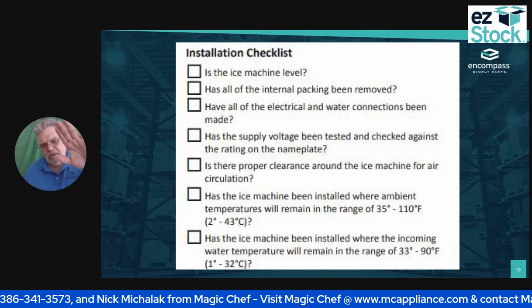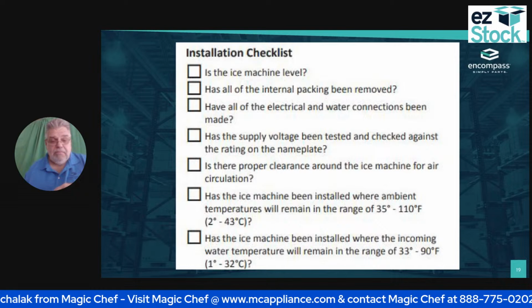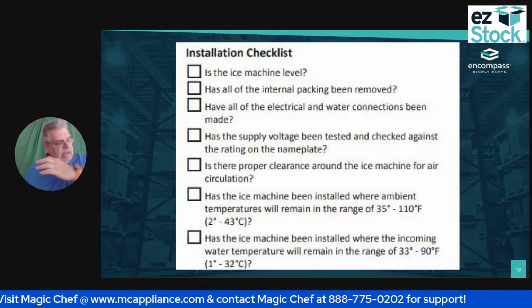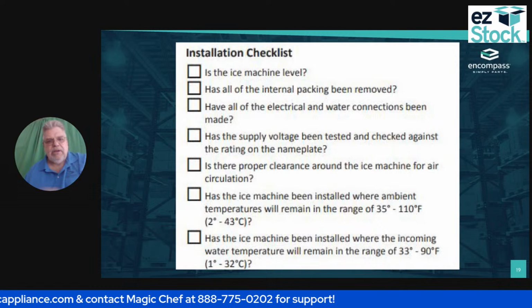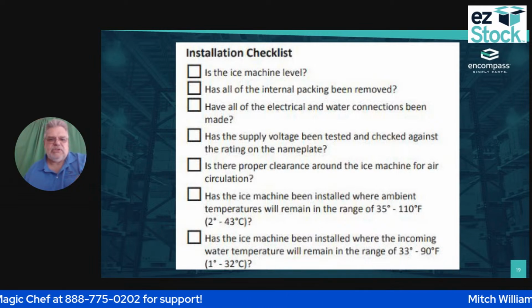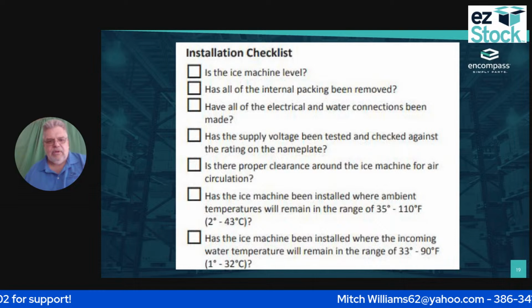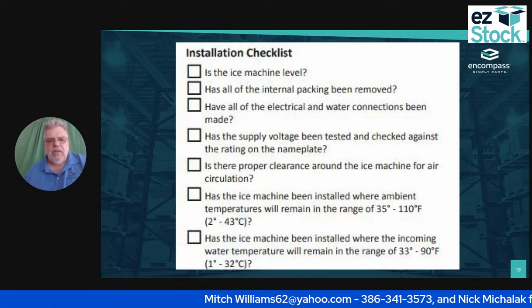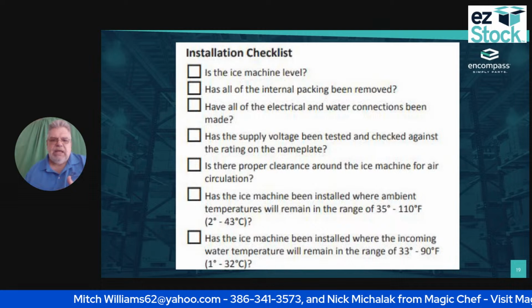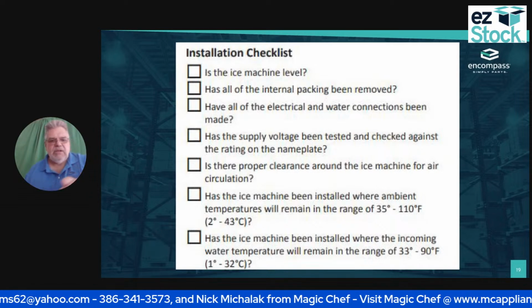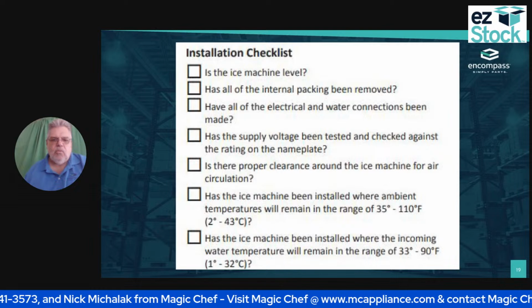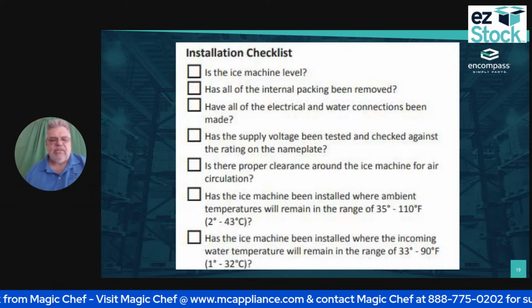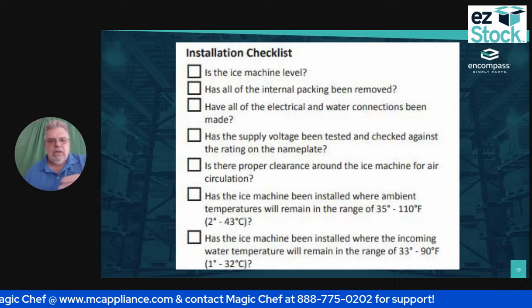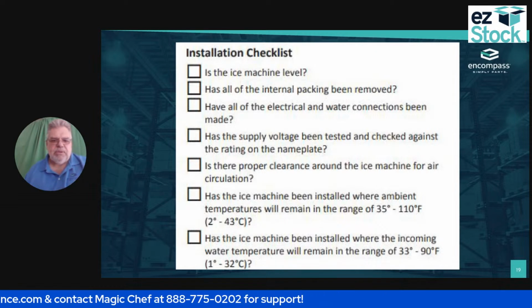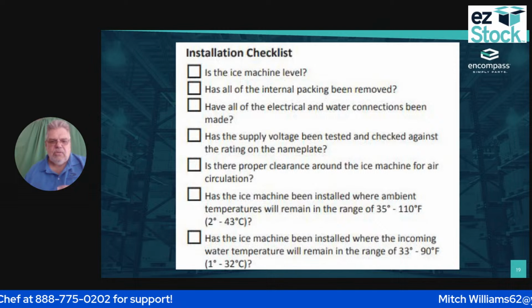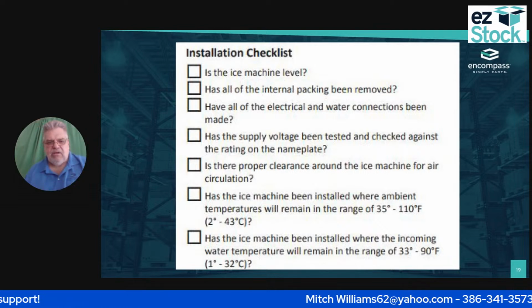I had it on my flip board, laminated with a piece of tape over it, so I could check the items off and wipe it clean with alcohol. Is the ice machine level? Has all the packaging been removed? Have all the electrical and water connections been made? I still checked that as part of my checklist. Has the supply voltage been tested and checked against the rating on the nameplate? I always made sure that happened too.